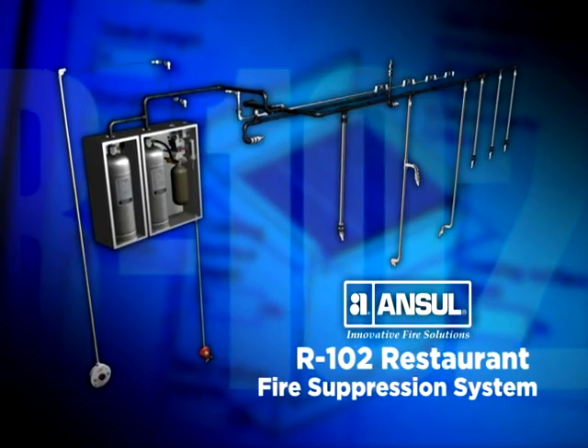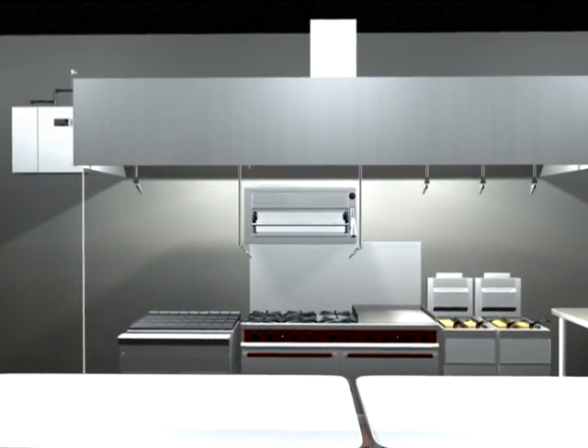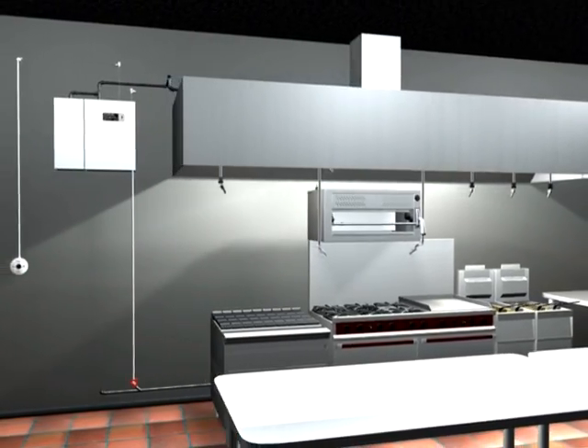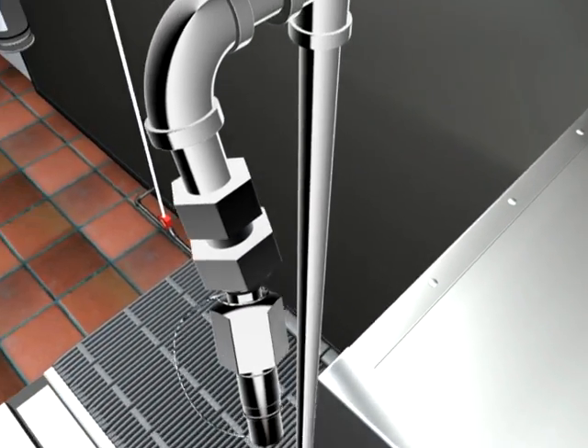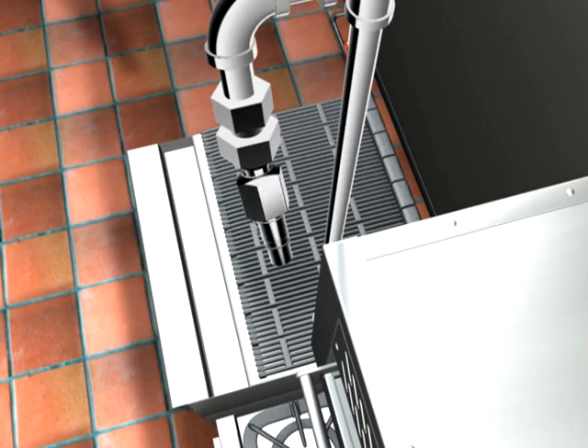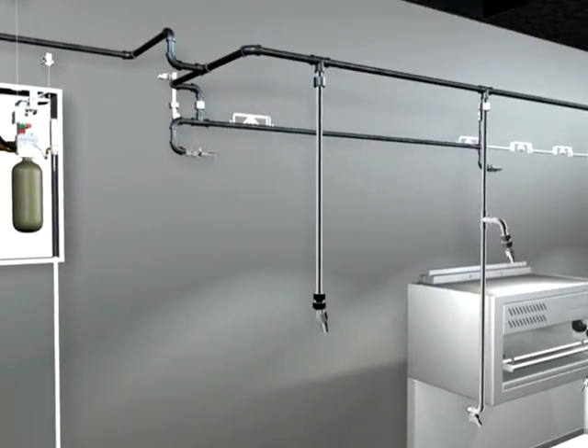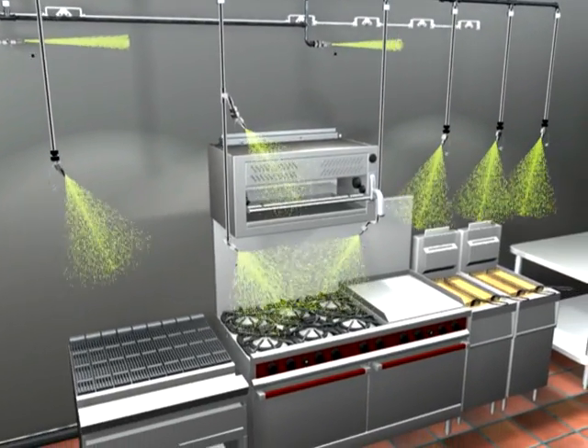The ANSUL R-102 Restaurant Fire Suppression System provides you with two design options. The primary is an appliance-specific design where nozzles are aimed at specific hazard areas of the appliance. This is considered the most economical design because the agent is aimed only where it is needed.